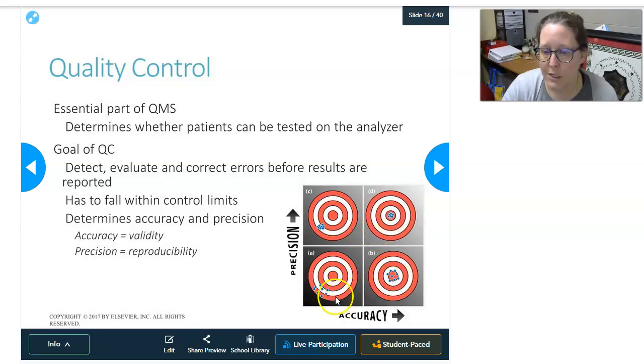These show low precision because you can see the dots are scattered around. It means that every time it's hitting a little bit off from what it's supposed to be. So what you definitely don't want for your analyzer is low precision and low accuracy. You're off center and all over the place. You do not want that. And here you're accurate but imprecise, meaning you're hitting all over, but they're still around what the true value is.